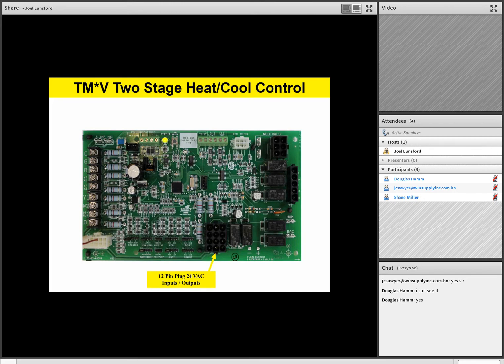Now, because this is a variable speed ECM motor, we're going to set up airflow with jumpers instead of hard physical terminals like we have on our previous boards. So all of your airflow jumpers and your configuration for the board are going to be found about in the middle of the board, at the bottom of the board. And so let's start looking at those jumpers right now.